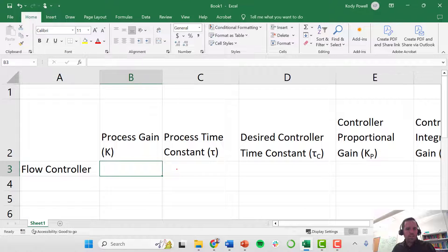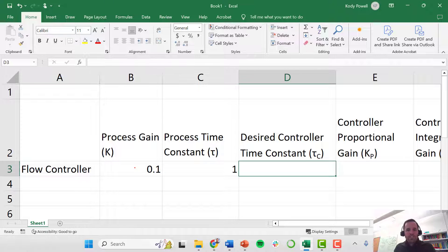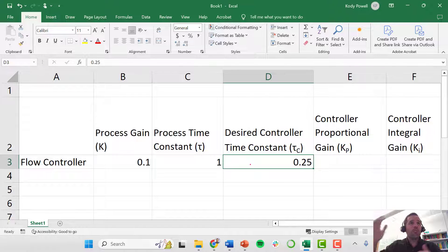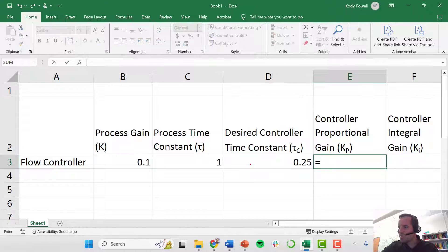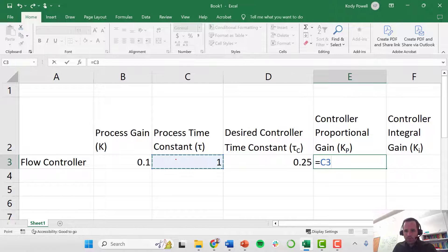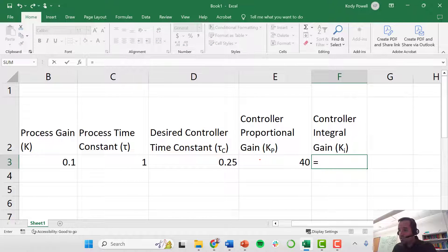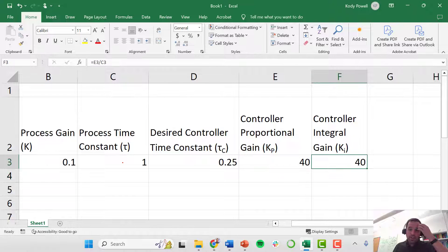I've created a simple Excel spreadsheet. Our process gain is 0.1, our process time constant is one minute. For the desired controller time constant, let's say we want to speed this process up and have it respond on a time scale of 15 seconds, or a quarter of a minute. Using the IMC tuning relationships, Kp equals the process time constant divided by the process gain multiplied by the desired controller time constant, giving us a Kp of 40. Our controller integral gain Ki equals Kp divided by tau, and since tau is one, Ki is also 40.